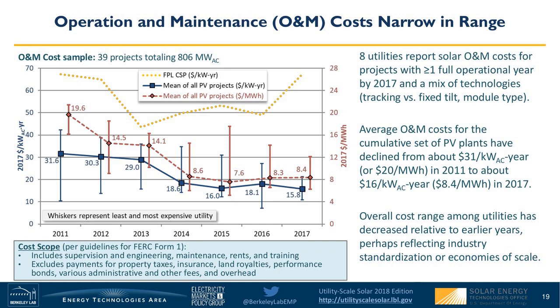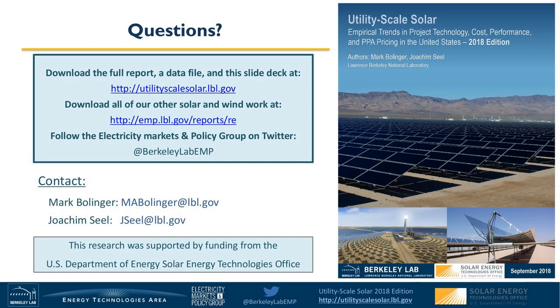Another one that came in: someone asked if I could explain a little more about the PV plus storage contract in Arizona. This is the APS First Solar project where APS will only pay for output, I think, between 3 and 8 p.m. What that means is that the project is set up to store all of the solar generation prior to 3 p.m. and then discharge it back to the grid during that 3 to 8 p.m. window.